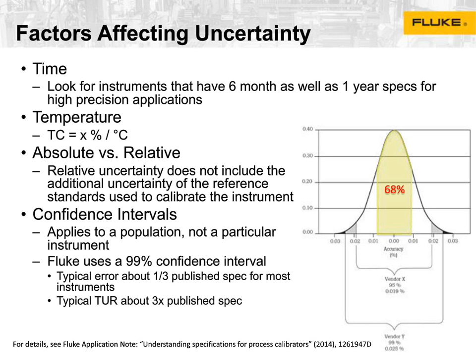One of the things that you'll start to see is that a lot of the highest quality manufacturers are starting to quote 6-month specifications. So if you shorten the amount of time between when a gauge is calibrated and the next time it's calibrated, you can actually tighten the specification. And so some manufacturers have started quoting 6-month specifications on their gauges for the most high accuracy applications. So people in custody transfer are using these kinds of specifications increasingly in order to reduce their error.